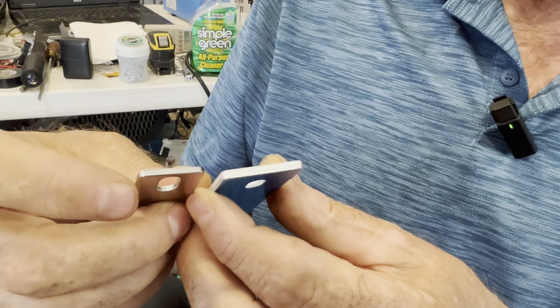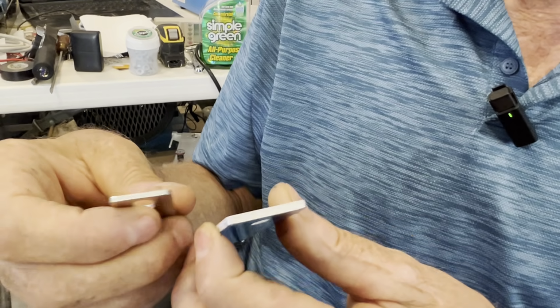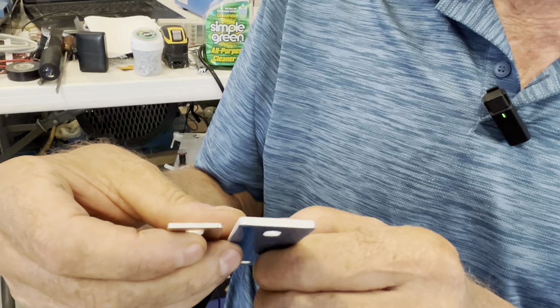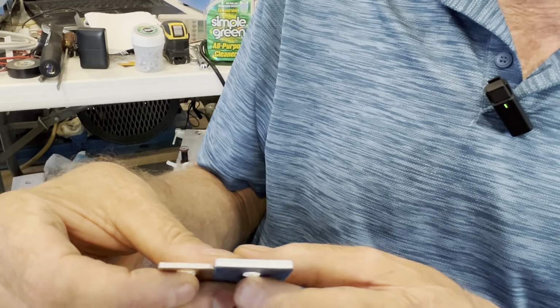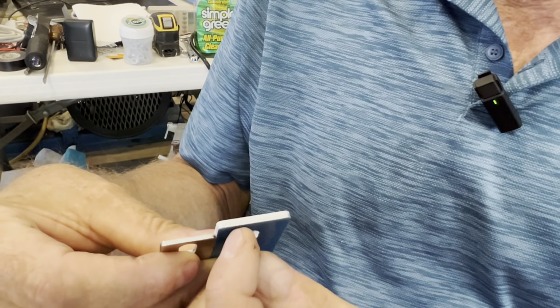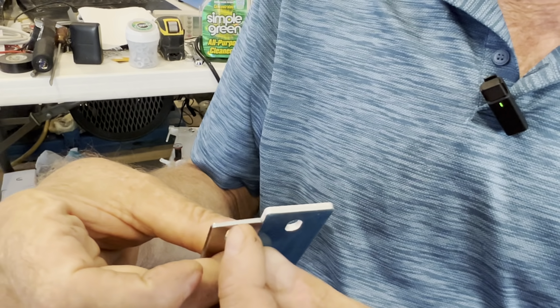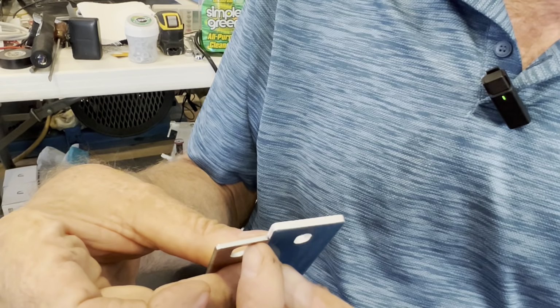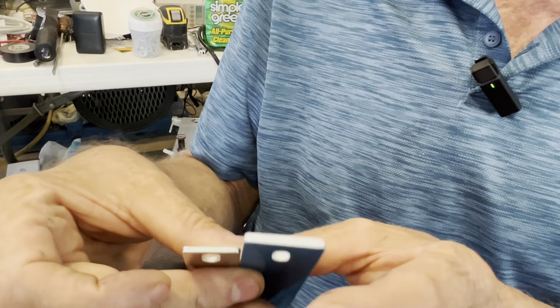They have to be larger because aluminum does not have the current carrying capacity that copper does. I measured these with my milliohm tester, and they have the same amount of resistance, but this is how much larger aluminum has to be in order to have the same resistance as copper of this dimension.